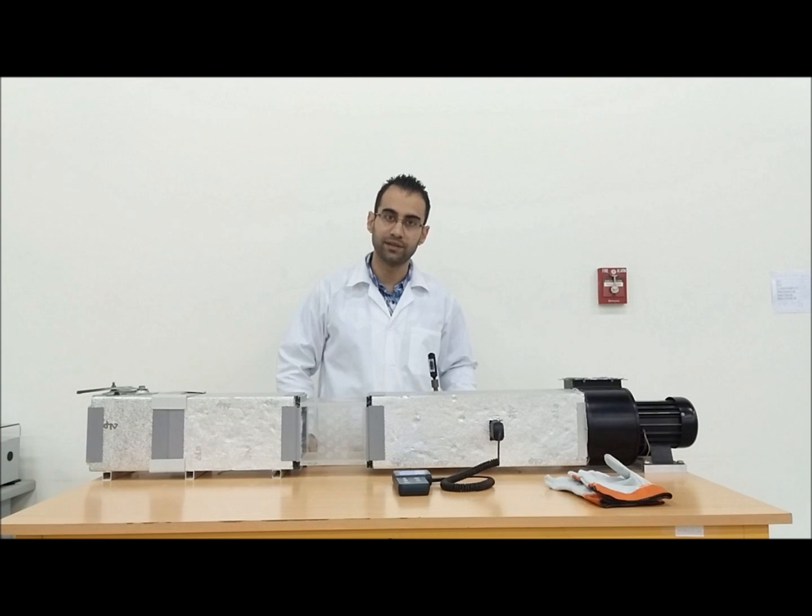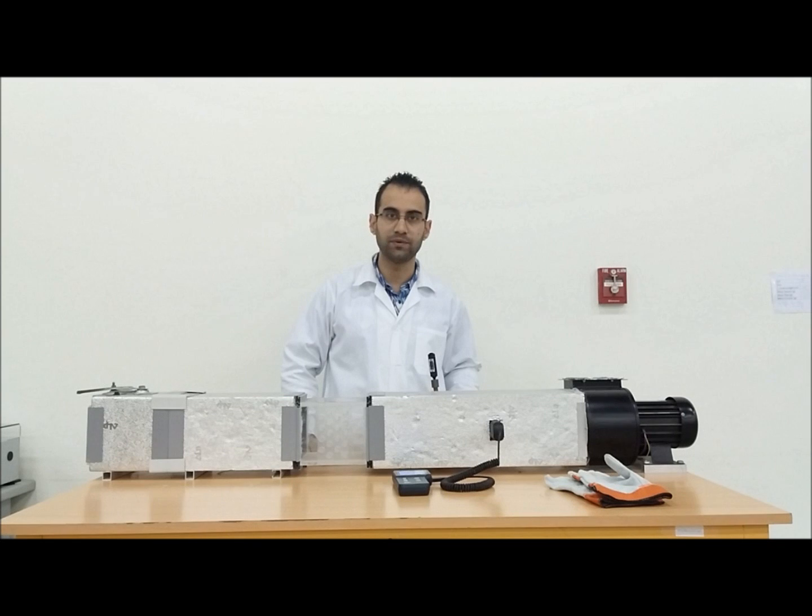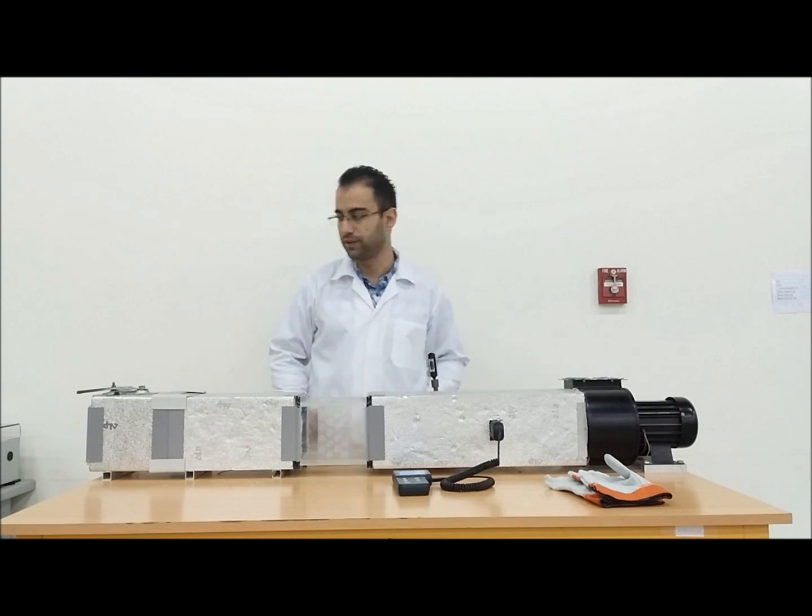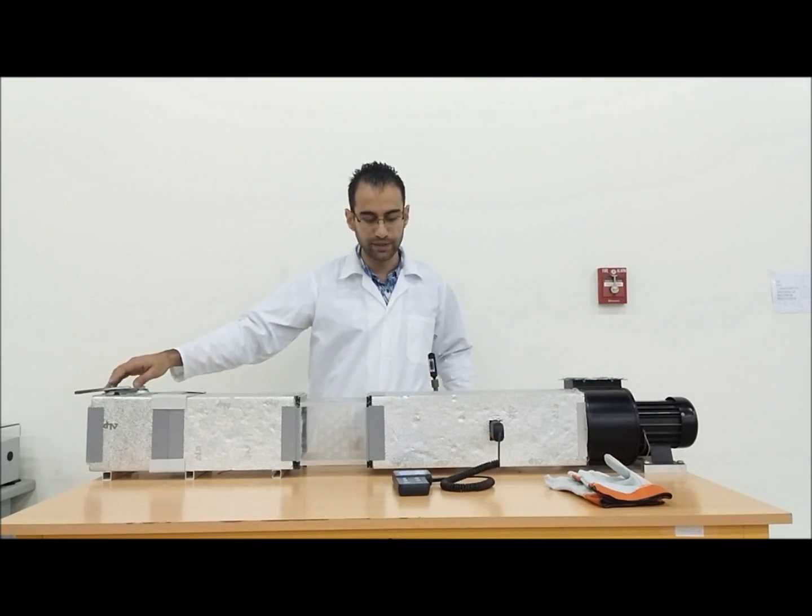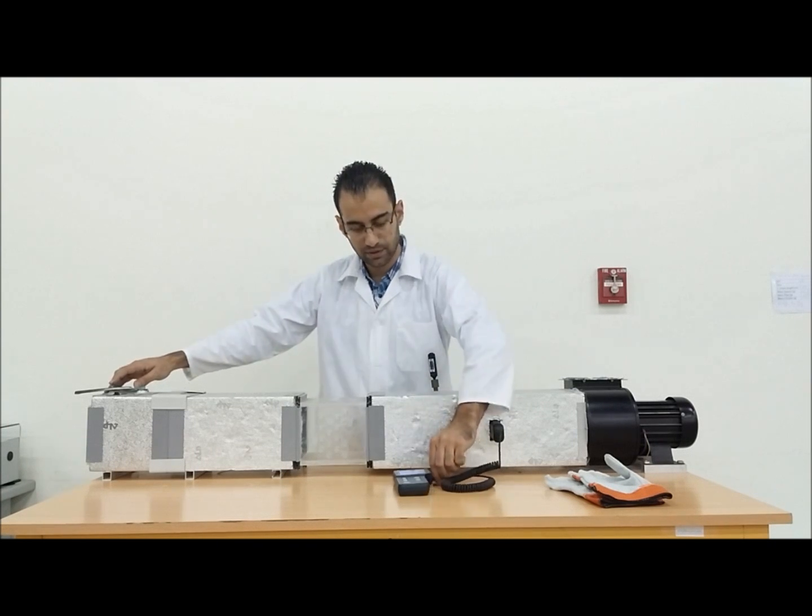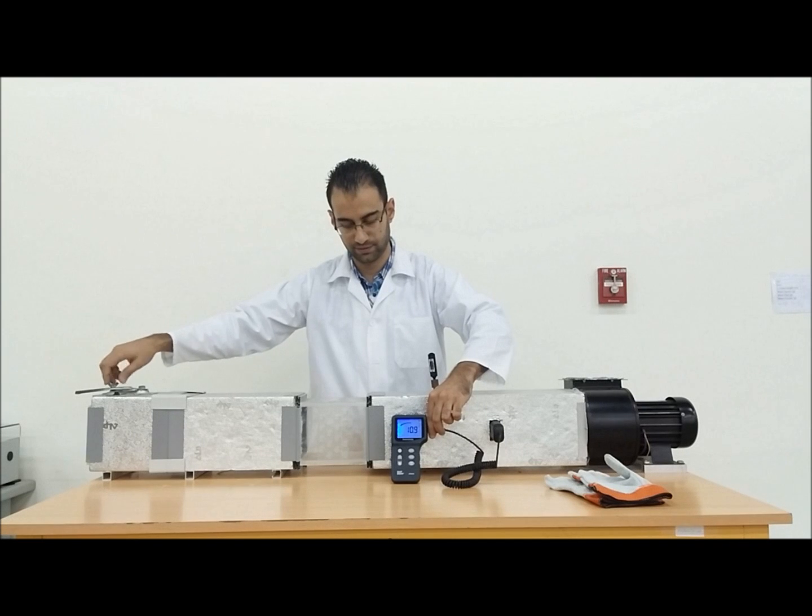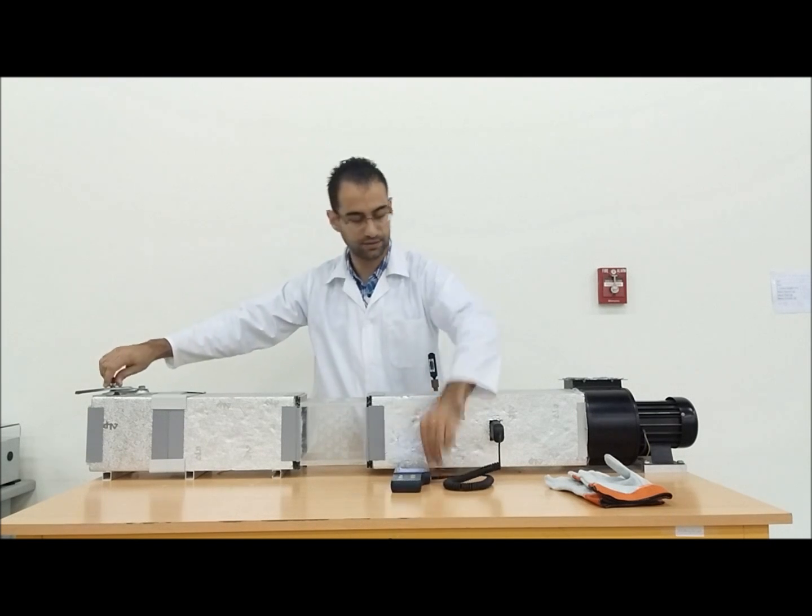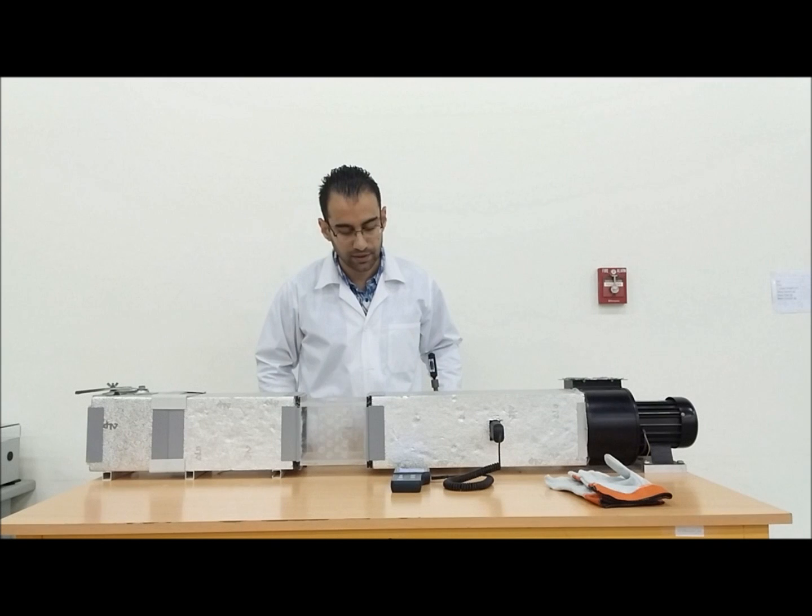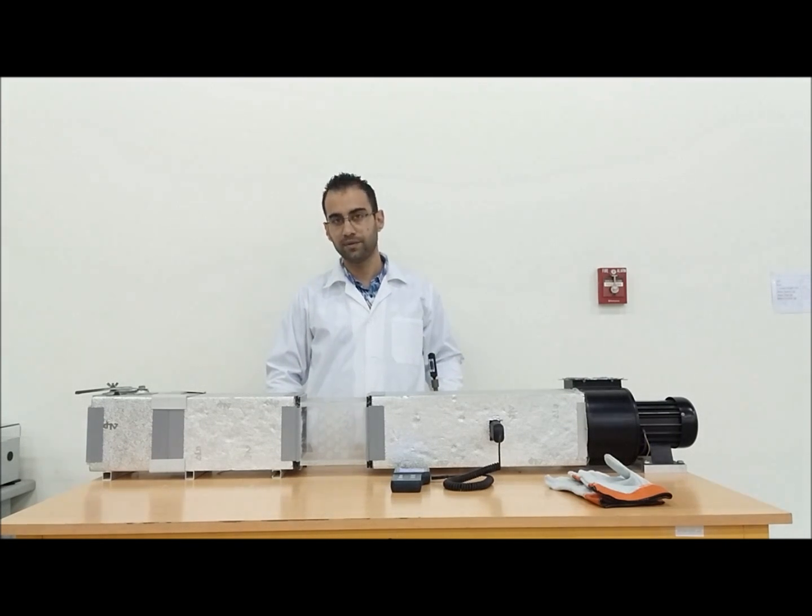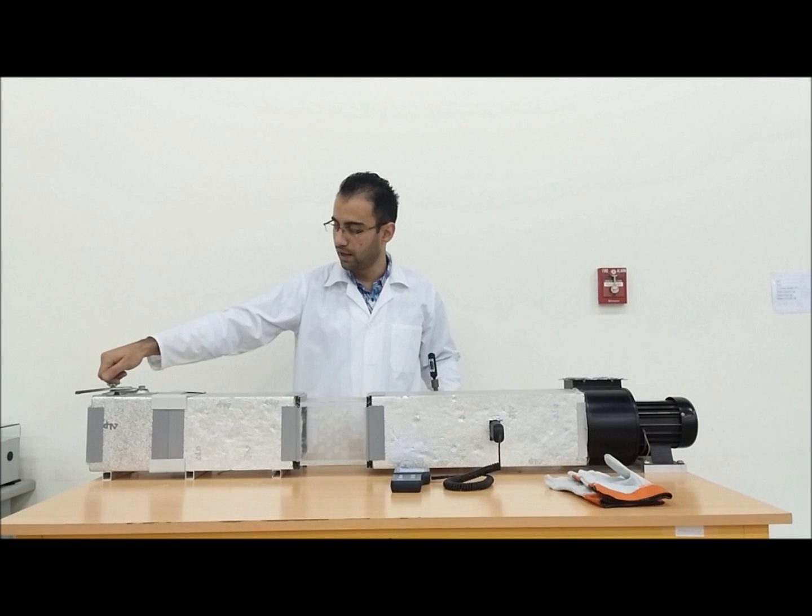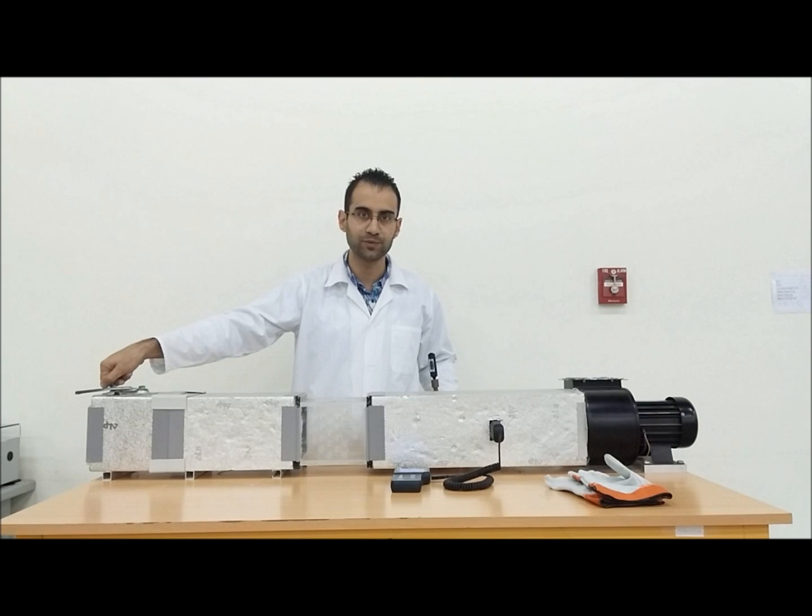We are going to set the air flow before the start of the experiment before getting a full set of readings. So I am going to do that quickly now. I got about 11 meters per second flow at this point. I locked the volume control damper so it doesn't change while we are undertaking the experiment.